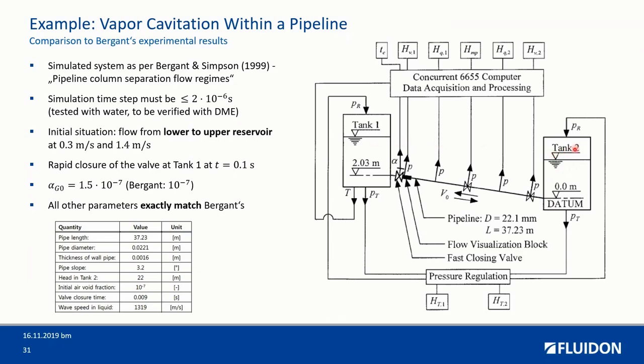Both of these tanks are pre-charged and because the pressure in this tank is higher than in this tank, we basically get a flow that goes like that. And at a certain point of time, this valve here is suddenly closed. So the liquid flowing like this basically sees a dead end all of a sudden, and that leads to a shockwave which travels through the system.